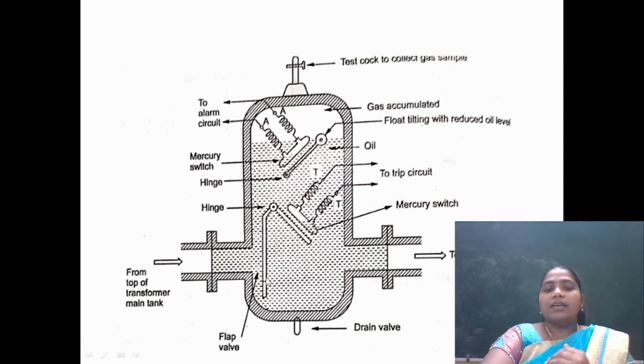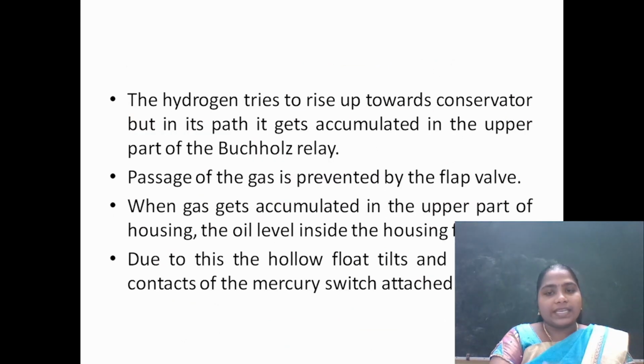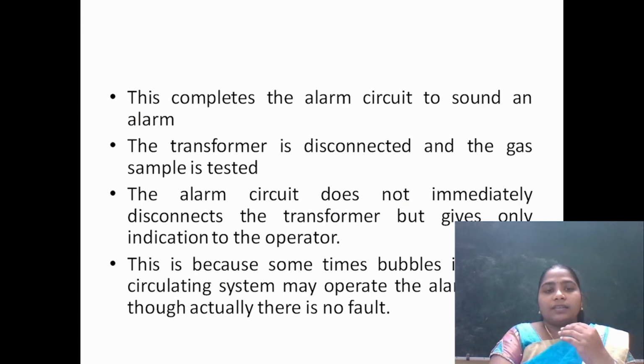Next, when the oil decomposes, the hydrogen tries to move towards the conservator. But due to the presence of this flap valve, the hydrogen gas moves upward. Here the hollow float tilts and gets connected with the mercury switch, so that it gives an alarm to the operator, so that the working of the transformer is stopped and part of the oil is tested. The alarm circuit does not immediately disconnect the transformer, but only gives a signal to the operator. This is because sometimes bubbles in the oil may operate the alarm circuit, though actually there is no fault.